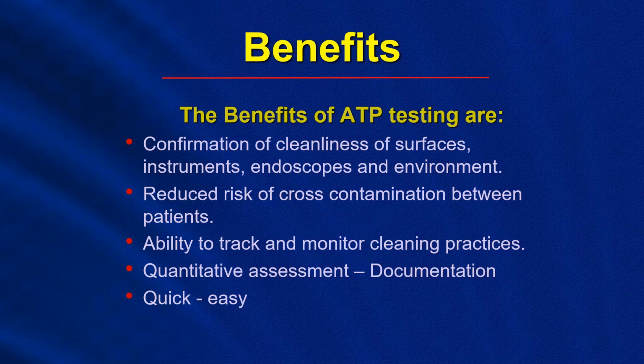With ATP bioluminescent testing devices, you get a quantitative assessment. So you will get a digital readout of a number, and you can use that for your documentation. Some devices will hook up to computers and you can run reports. If the Joint Commission happens to come in and is looking for documentation on your verification processes of cleaning and cleanliness, you can actually run reports. But more importantly, it's a quick and easy test. So with the ATP testing devices, you will get a measurement in as little as 15 seconds. In 15 seconds, you will get a readout of ATP.